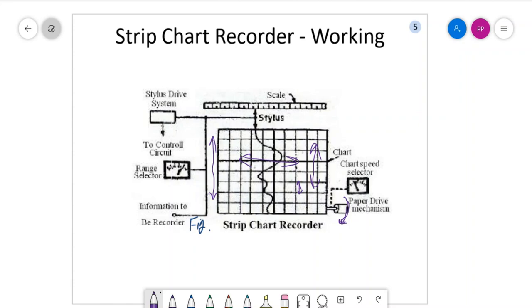You have a system for driving the paper at some selected speed — in most cases from one to one hundred millimeters per second. You have the stylus, which helps in printing through a linear shift mechanism. It moves horizontally and in proportion to the quantity to be measured, so this movement should be an exact replica of the measurement which is changing with time.